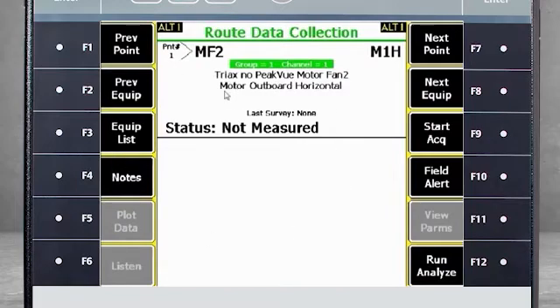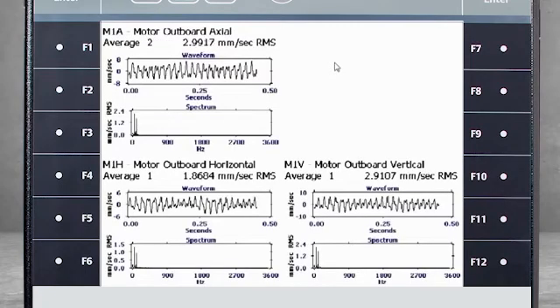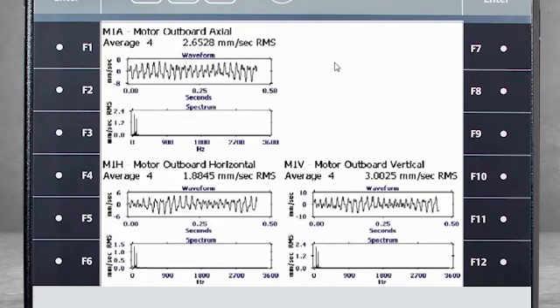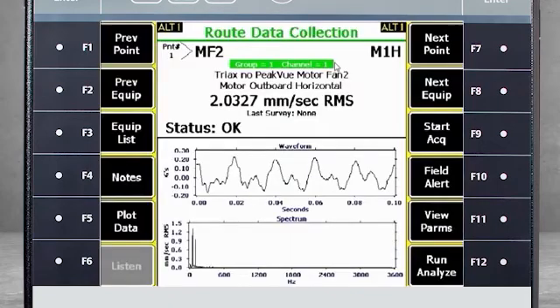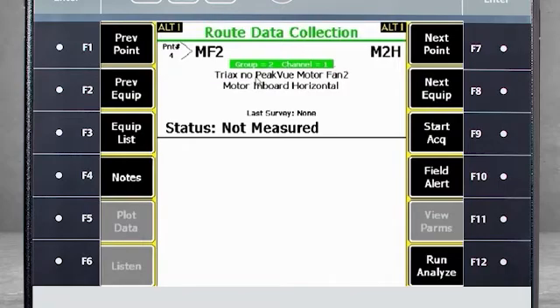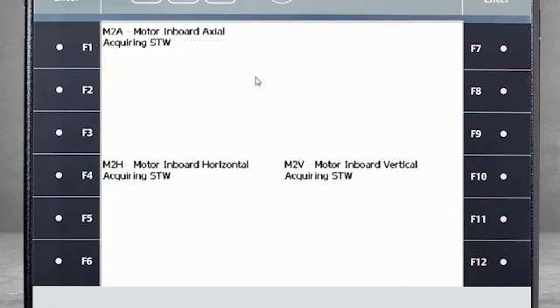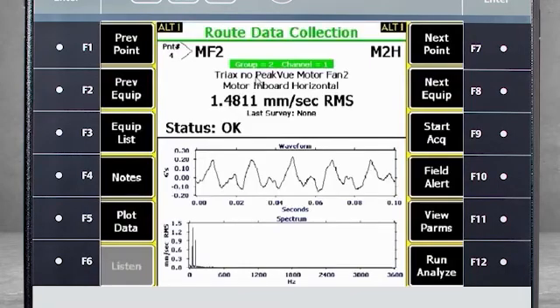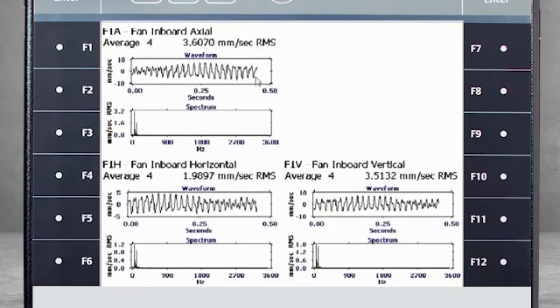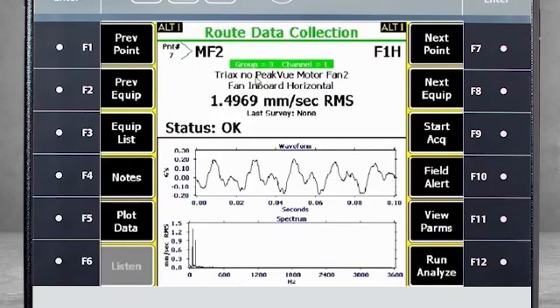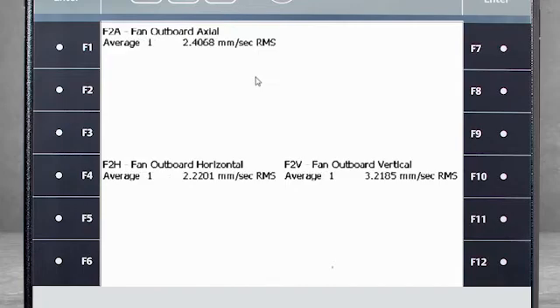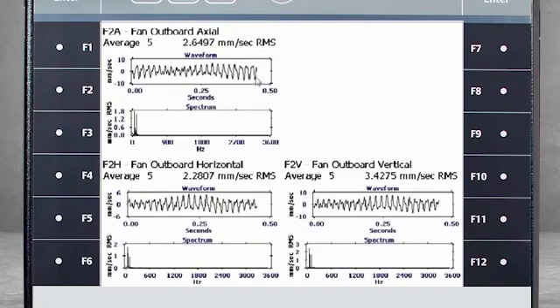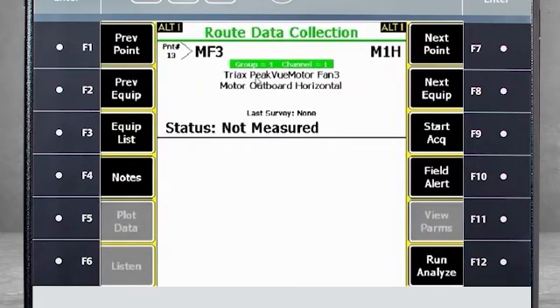We are at the motor outboard horizontal point, and you see that it is grouped. Push Enter, and you will see data is being acquired from three points simultaneously using triax sensors, and then jumps to the three points from the inboard side. Once the data is collected from the motor inboard, the collector jumps to the fan inboard, and eventually the fan outboard. This machine is now done.